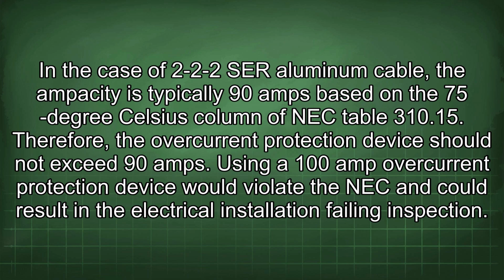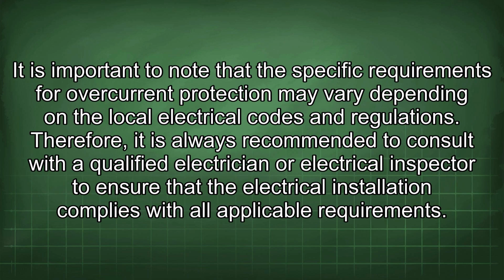In the case of 2-2-2 SER aluminum cable, the ampacity is typically 90 amps based on the 75°C column of NEC table 310.15. Therefore, the overcurrent protection device should not exceed 90 amps. Using a 100 amp overcurrent protection device would violate the NEC and could result in the electrical installation failing inspection. It is important to note that the specific requirements for overcurrent protection may vary depending on the local electrical codes and regulations. Therefore, it is always recommended to consult with a qualified electrician or electrical inspector to ensure that the electrical installation complies with all applicable requirements.